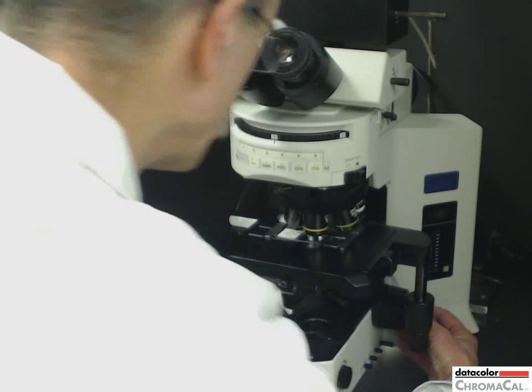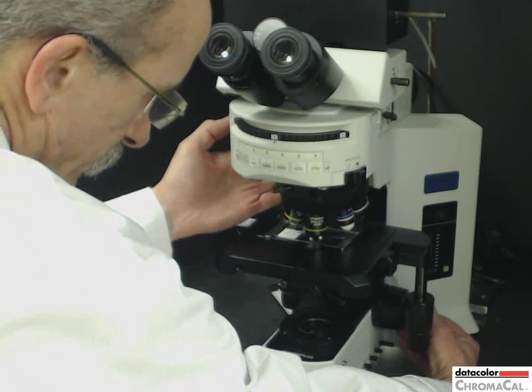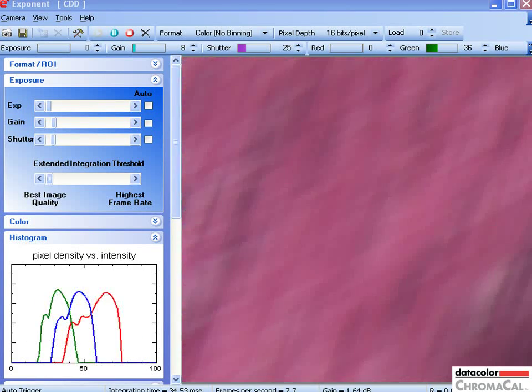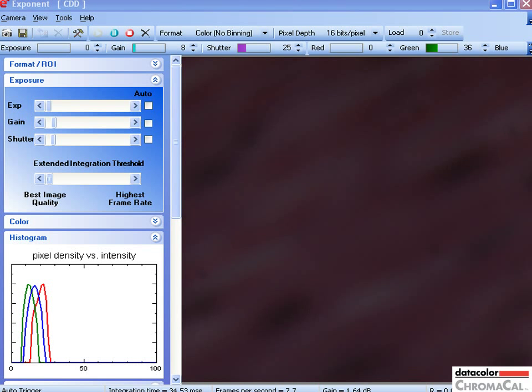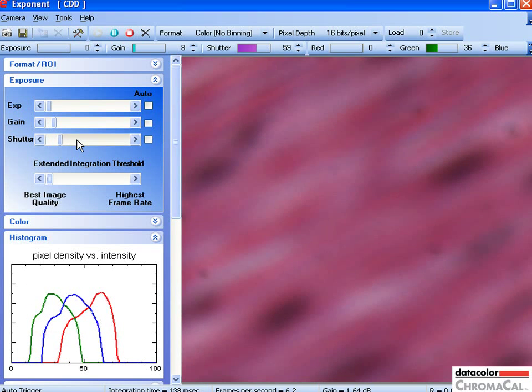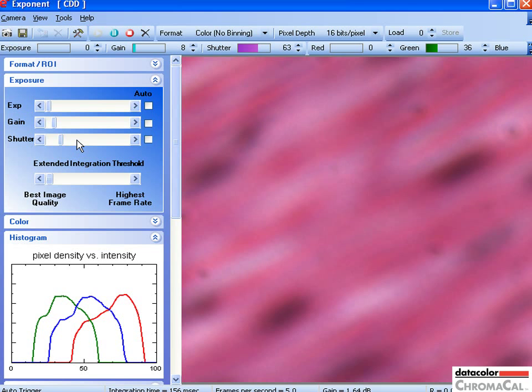When taking pictures, you will likely change objectives and the image will get darker or brighter. In the camera software, when you change objectives, you can see the image getting darker. Rather than turn up illumination on the microscope, focus and then adjust the exposure instead.